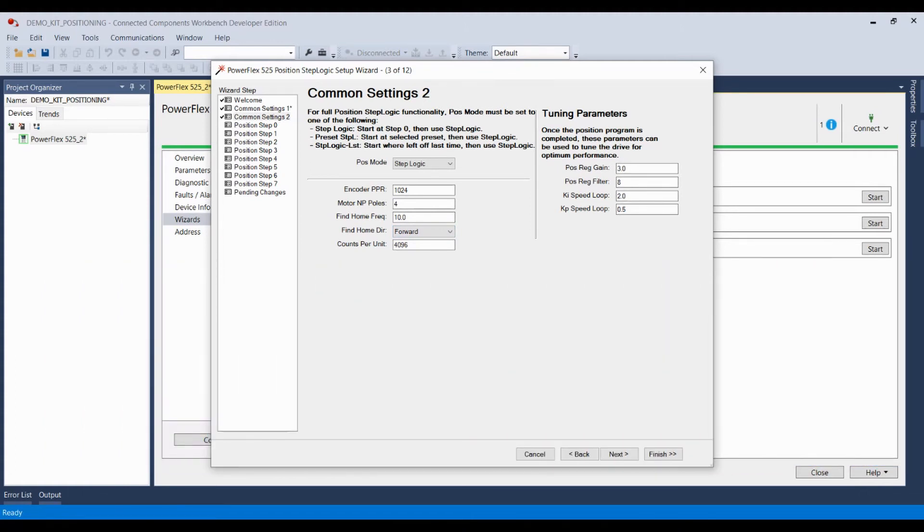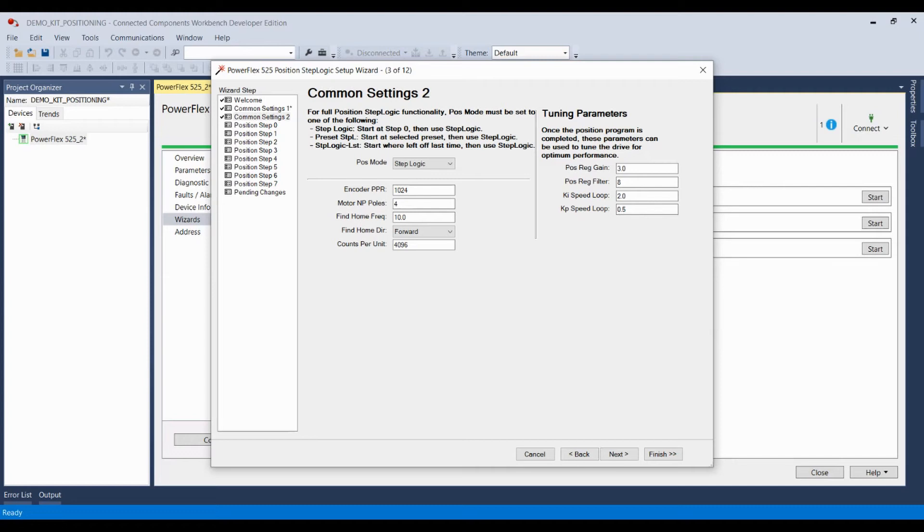Over here, you have your tuning parameters. If you're operating a position function in sensorless vector torque preference mode, you can use these to bump in your position regulator gain filter and speed loop settings to allow the drive to function optimally between position steps and as it ramps up and ramps down during a position step.